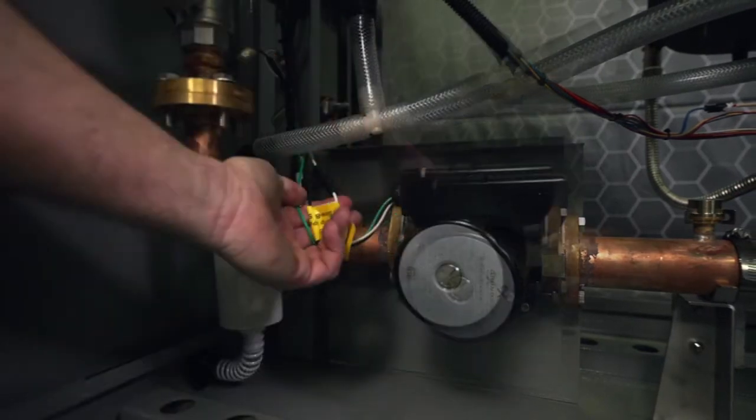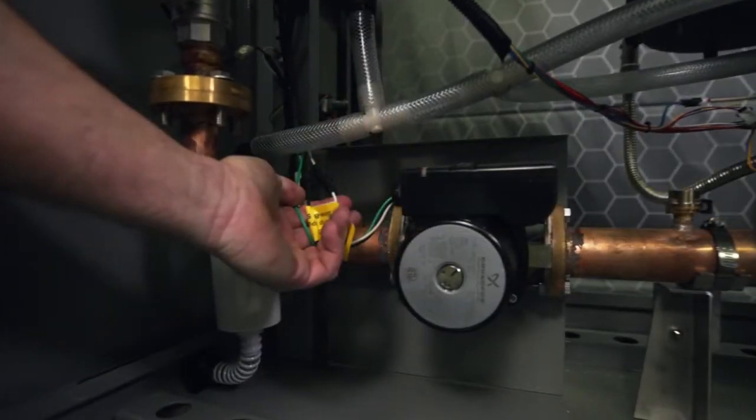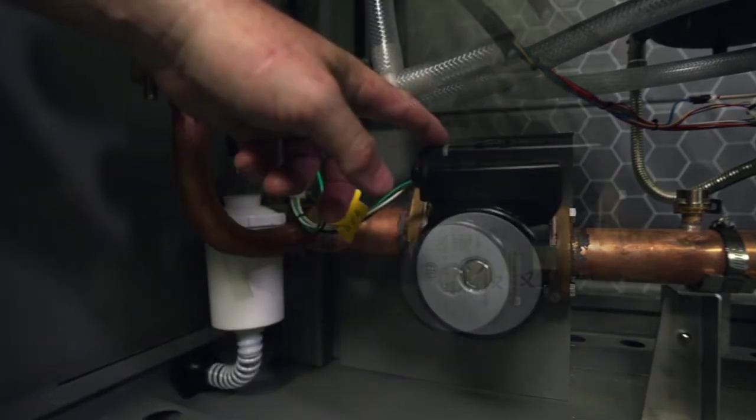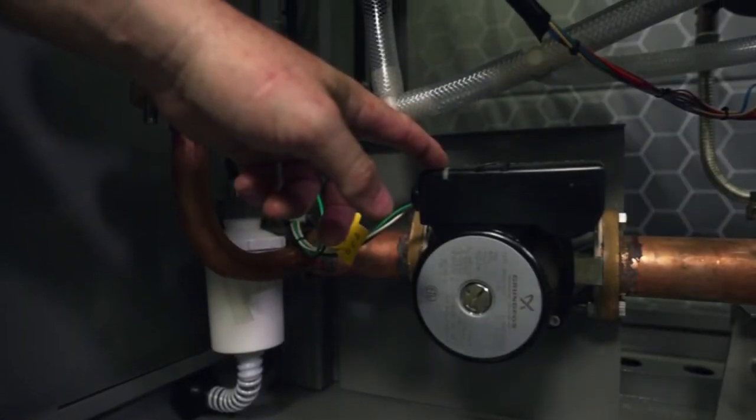If you have no green light on the pump, you will want to check the fuses in the black capsules on the wiring harness. You have 120 volts to the pump if you have a green light.